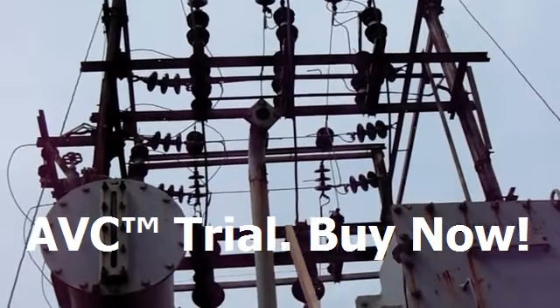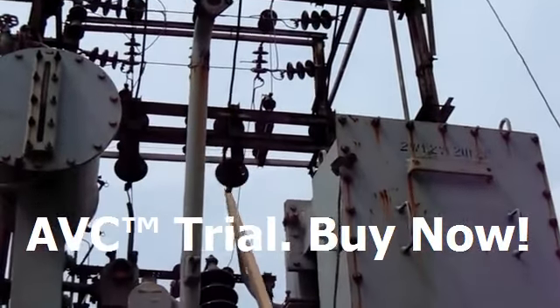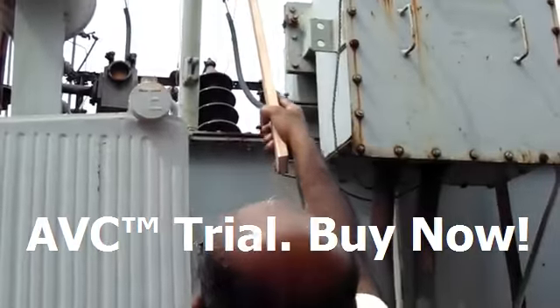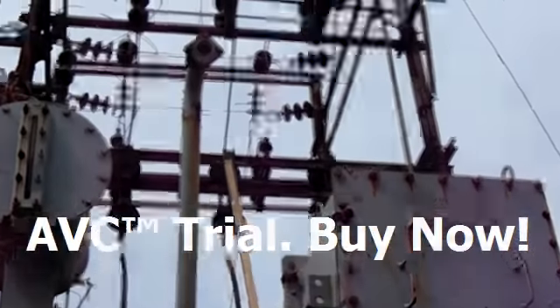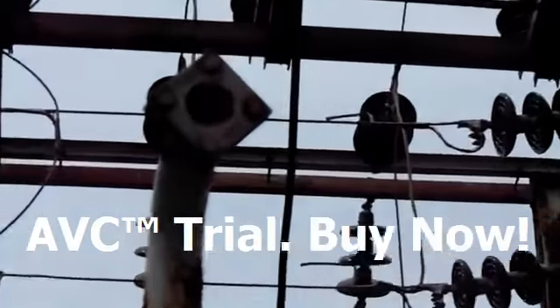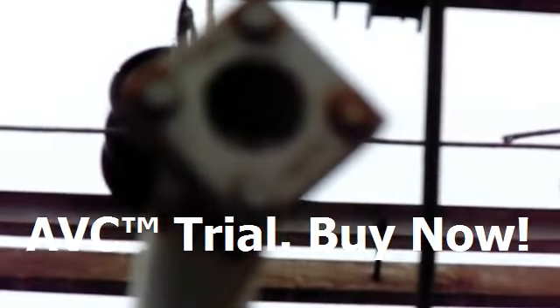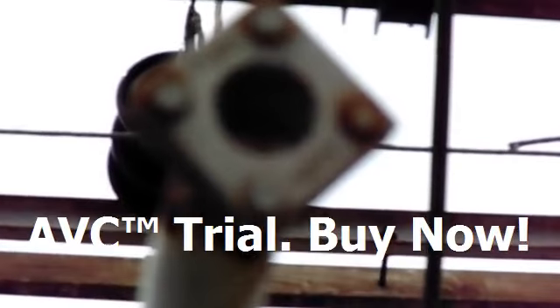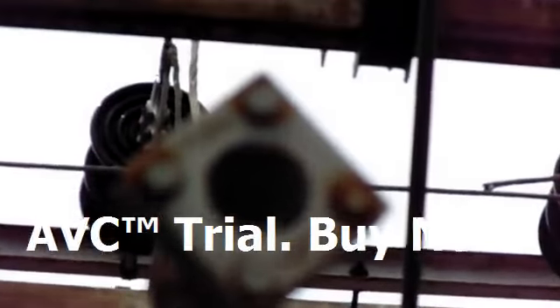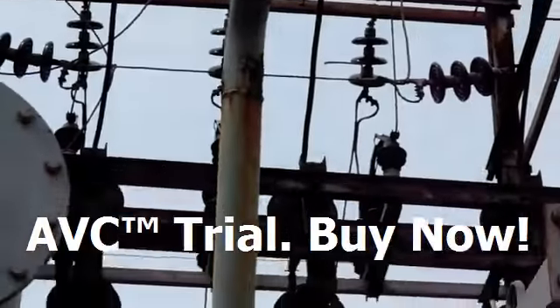Otherwise, if you don't take care, and if the pressure inside due to internal faults goes up, then the transformer may explode. So therefore, this acts as the pressure vent, and you see that it is slightly twisted at an angle. It is like that so that when it is raining, no water should go inside. That is why it is slightly tilted like this. And then the other important thing you can see is this, the protection relay, which you can see.